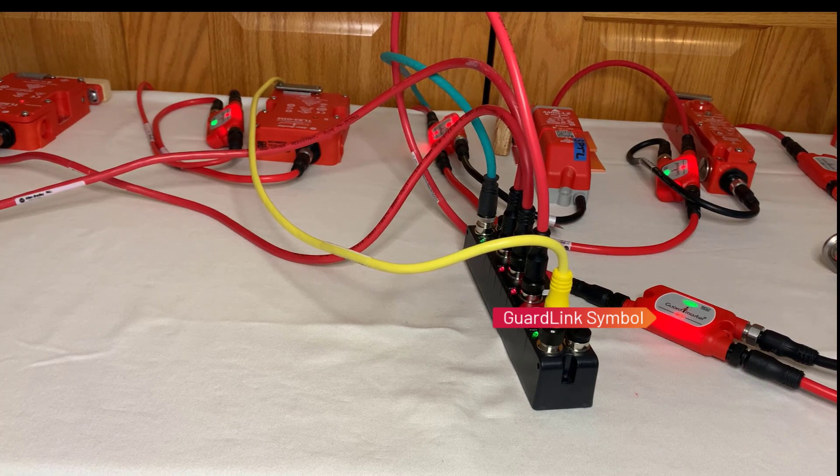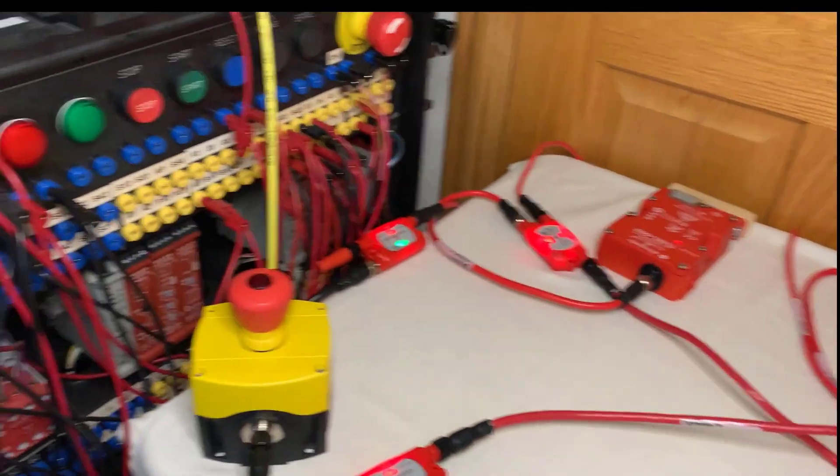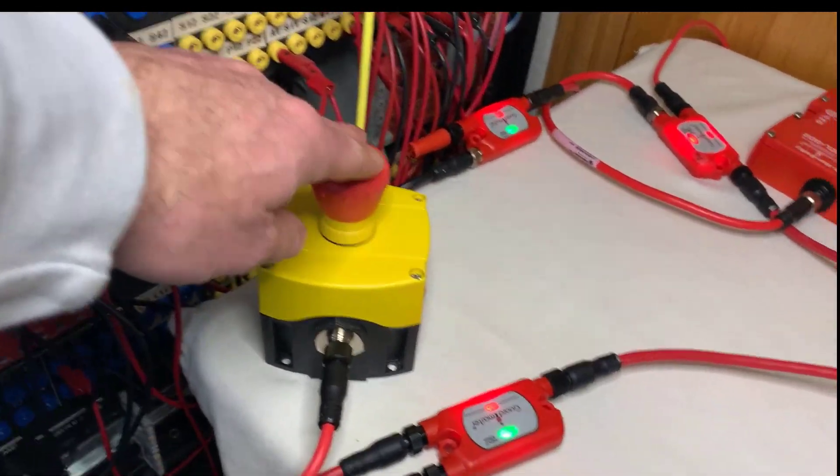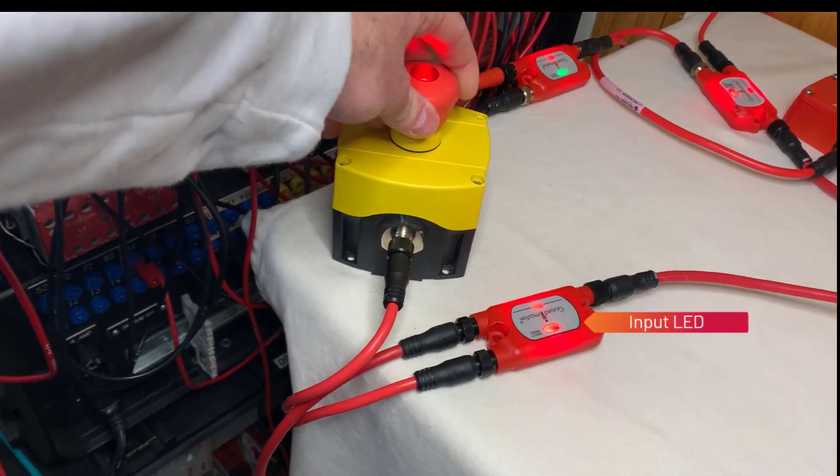Taps with safety inputs that are indicating a run-ready state, like e-stop not pressed, non-locking guard doors closed, and locking guard doors closed and locked, should have the input LED flashing green.